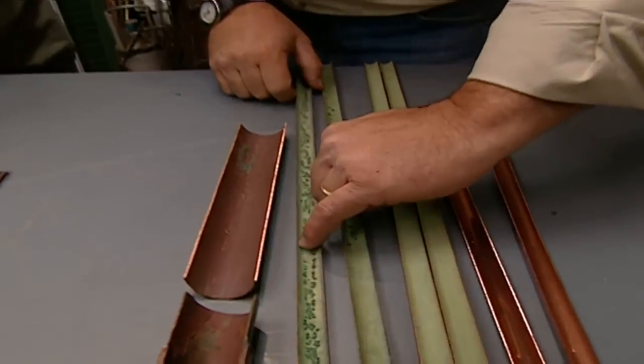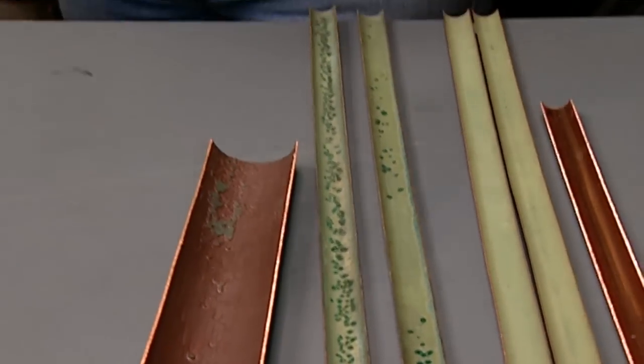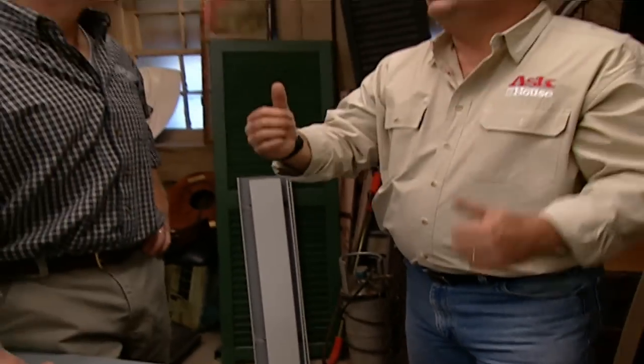Well, on the water heater, on a new installation, if you can change that anode rod every 3 to 5 years and stay on top of it, you can get a water heater to last a long time. If it's been more than 10 years, don't even bother with the water heater. If it's on the cold water side, you see pit corrosion, you would suspect flux. So you really have to decide, is it on the hot or the cold? If it's on both, have your water tested.